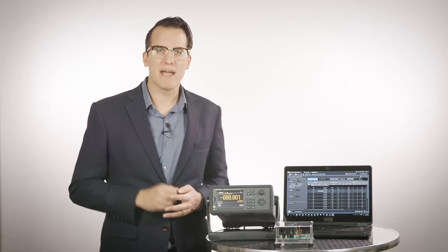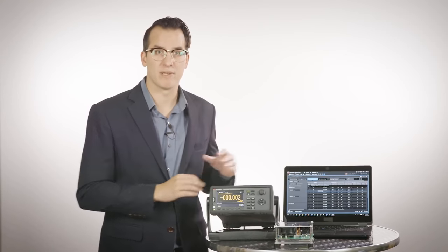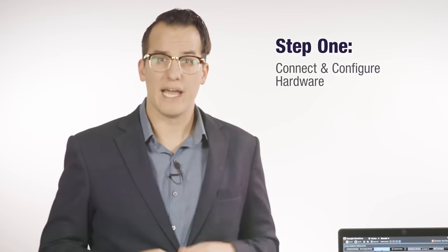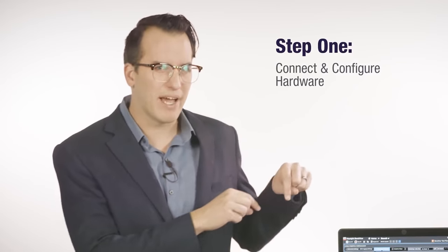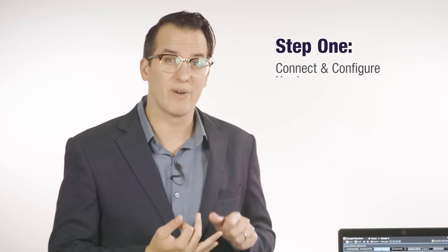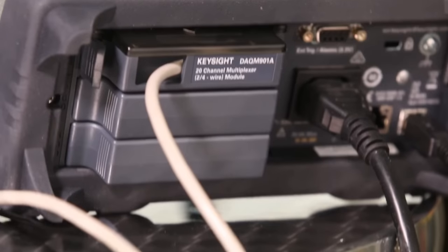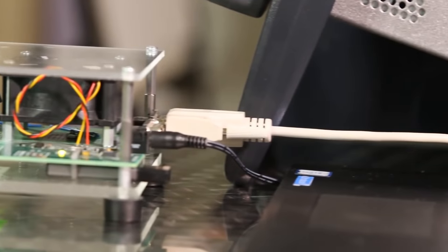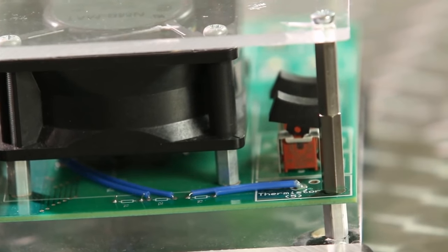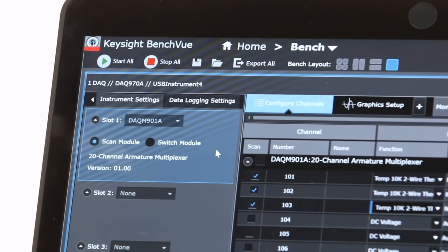So there are three main steps to making a temperature measurement. First, we need to connect and configure our setup. In this case we're going to use the DAQM901A module's channels 101, 102, and 103, which are wired to the temperature cube thermistors T1, T2, and T3. Then we're going to open up BenchVue and make sure we're connected and ready to configure our DAQ.